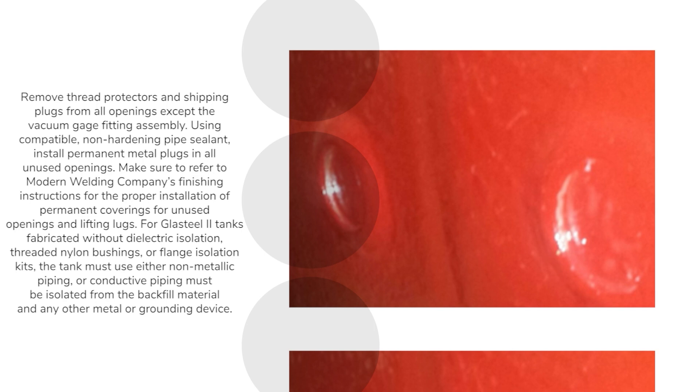Make sure to refer to Modern Welding Company's finishing instructions for the proper installation of permanent coverings for unused openings and lifting lugs. For Glasteel II tanks fabricated without dielectric isolation, threaded nylon bushings or flange isolation kits, the tank must use either non-metallic piping, or conductive piping must be isolated from the backfill material and any other metal or grounding device.